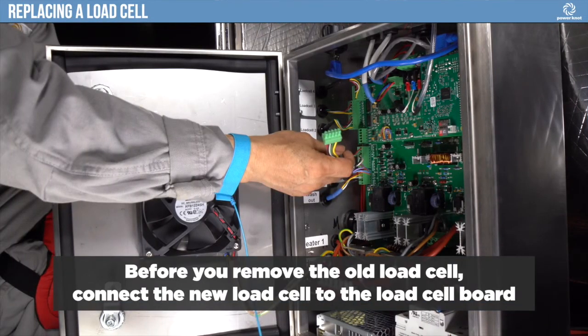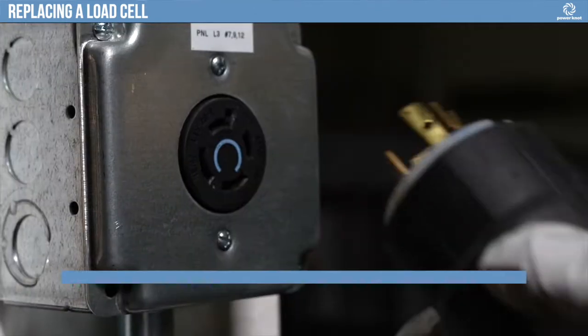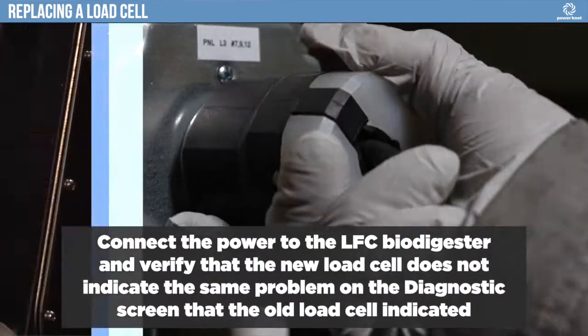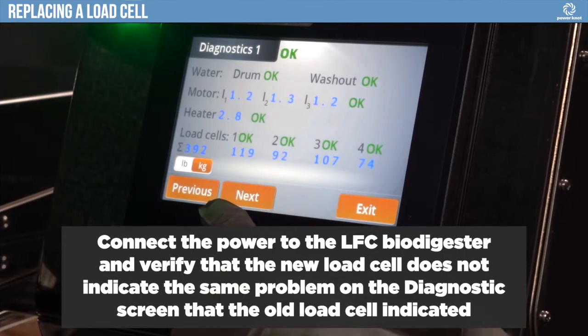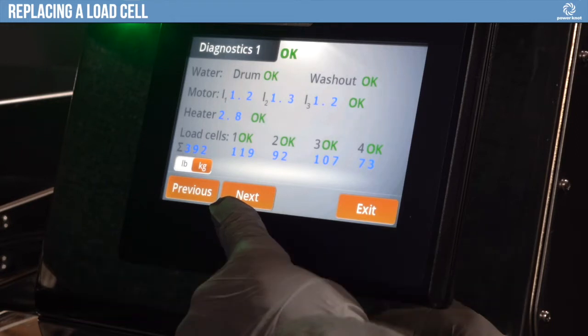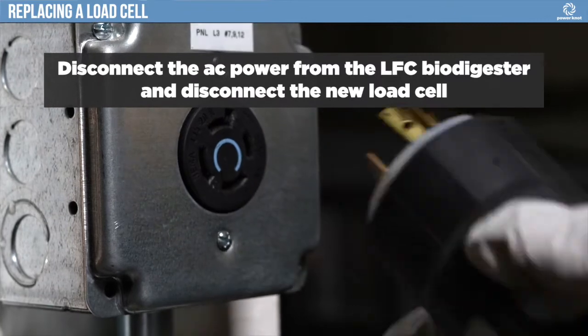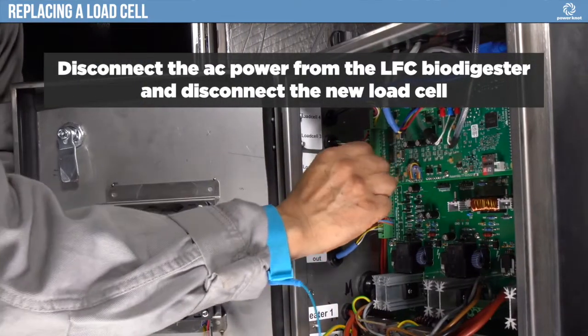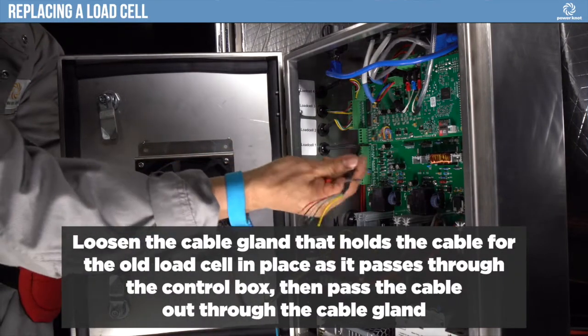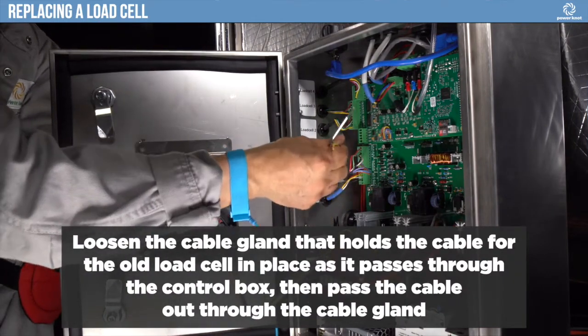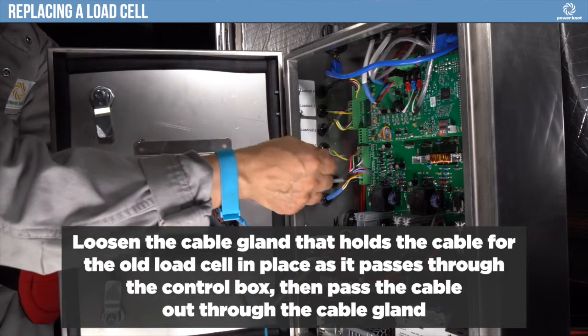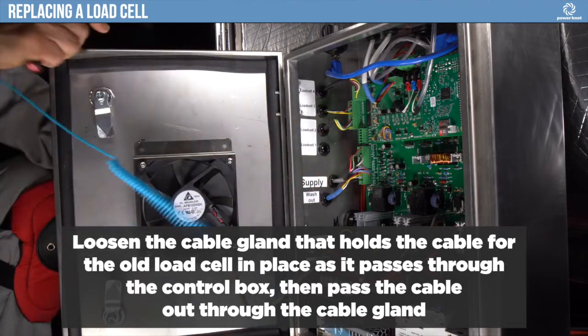Before you remove the old load cell, connect the new load cell to the load cell board. Connect the power to the LFC biodigester and verify that the new load cell does not indicate the same problem on the diagnostic screen that the old load cell indicated. Disconnect the AC power from the LFC biodigester and disconnect the new load cell. Loosen the cable gland that holds the cable for the old load cell in place as it passes through the control box, then pass the cable out through the cable gland.